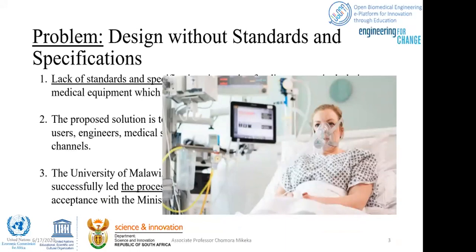When designing a breathing aid machine, one must consider the mouthpiece — whether invasive or non-invasive. Invasive means being plugged into the human body or face, with pipes going through the throat, nostrils, or mouth. Either way, you need to know the sizes, standards, and specifications — for example, how much diameter of a pipe can fit into a person's nostril, whether they are a baby or an adult in critical care.